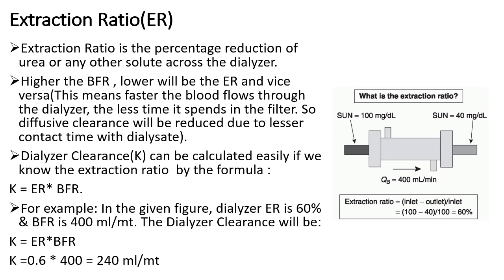In the given figure, the extraction ratio is 60% and blood flow rate is 400 ml per minute. Calculating dialyzer clearance as the product of extraction ratio and blood flow rate gives us 240 ml per minute — that is your dialyzer clearance.